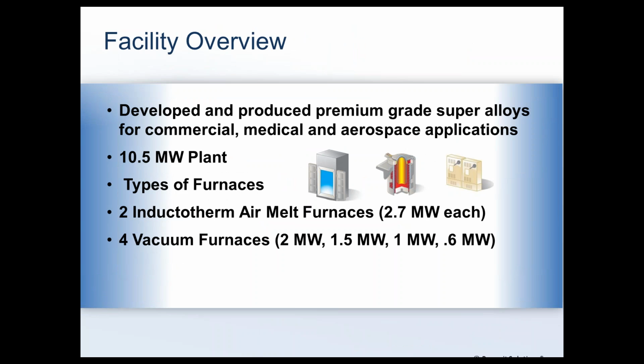Cannon Muskegon is a producer of master alloy for the investment casting and aerospace industry. We operated a facility with 6 furnaces in it. They were 4 vacuum furnaces that comprised a 2,000 kW power supply, a 1.5 megawatt or 1,500 kW, 1,000 kW, and a 600 kW. And then they had 2 air melt induction furnaces that were 20,000 pound furnaces, and they were operating at a 2.7 megawatt or 2,700 kW power setting.